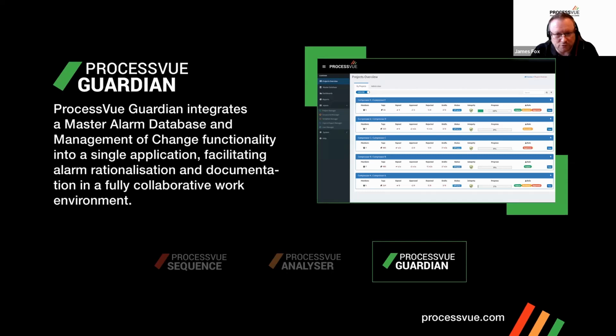It integrates an approval workflow. So we have roles within the software. Reviewers will make changes and approvers will sign those changes off before they can be deployed back to the host alarm systems. And this cuts down on the number of unauthorized changes that are being made to your alarm settings. When it comes to optimization and rationalization of your alarms, we have productivity tools built into Guardian that help speed up the whole rationalization and optimization process. We have features such as copy one alarm configuration to many and bulk or batch edits, where you can edit hundreds of tags and alarms in a single pass.